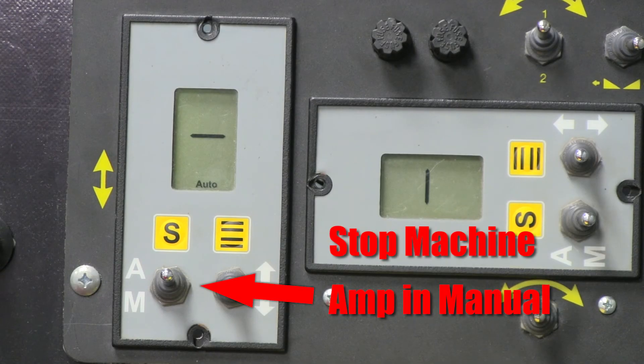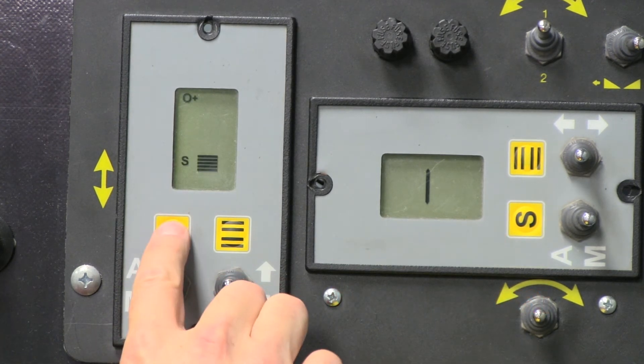Sensitivity refers to how fast the machine will respond to a deviation from a sensor. You should always make changes to your Smart Amps while the machine is stopped and the Smart Amp is in manual. To adjust the sensitivity, press the S button.